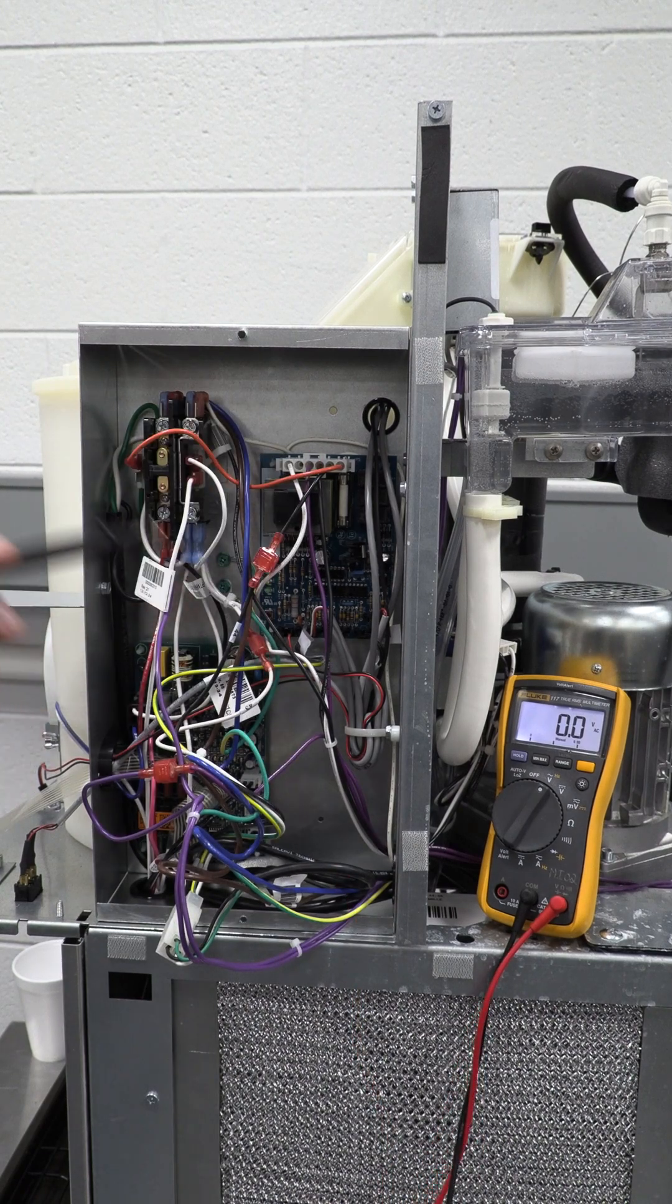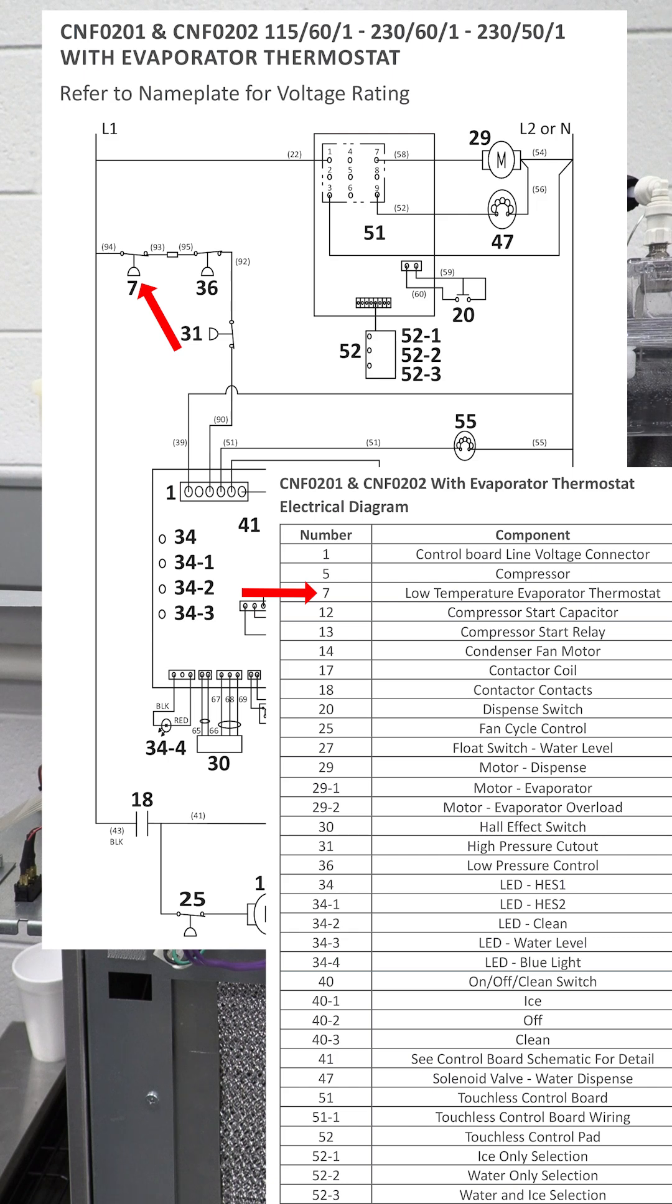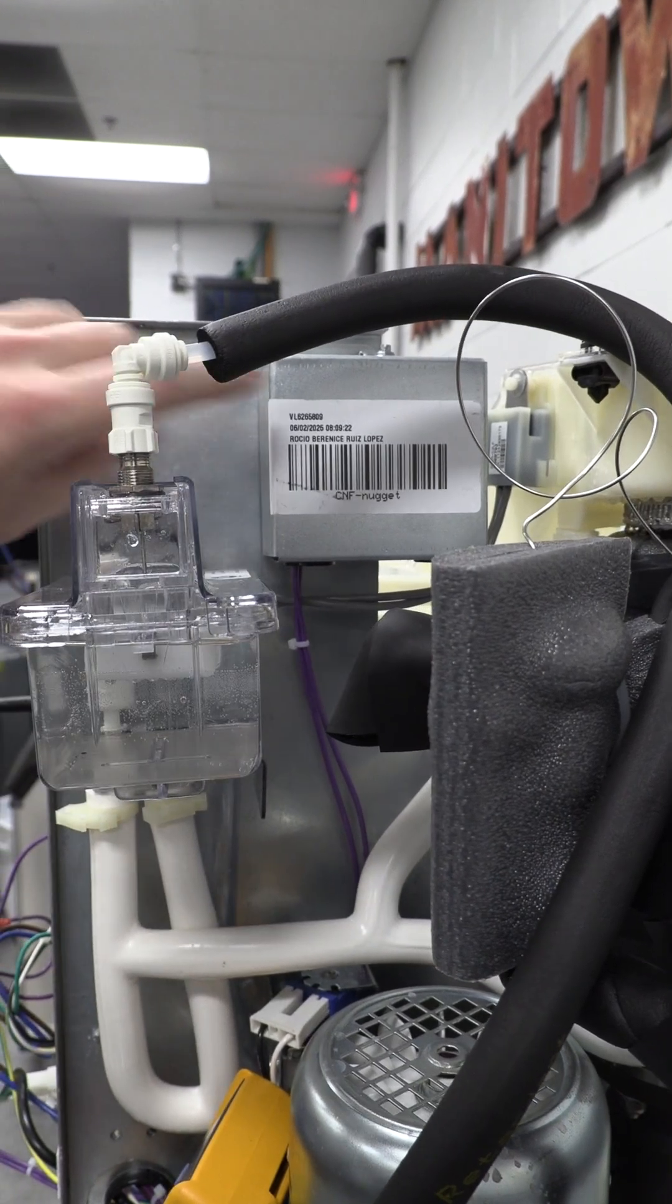I'm going to start with connecting one of my leads to the neutral. If we take a look at the schematic, you'll see that the line voltage travels through component number seven. Taking a look at the electrical chart, you'll see that component number seven is the low temperature evaporator thermostat.